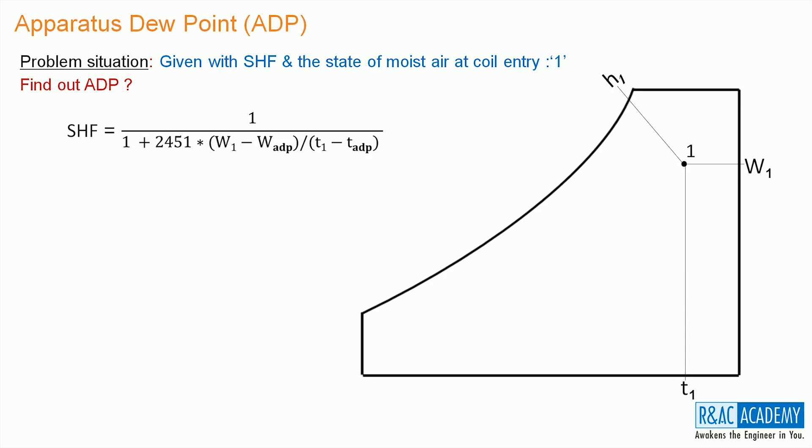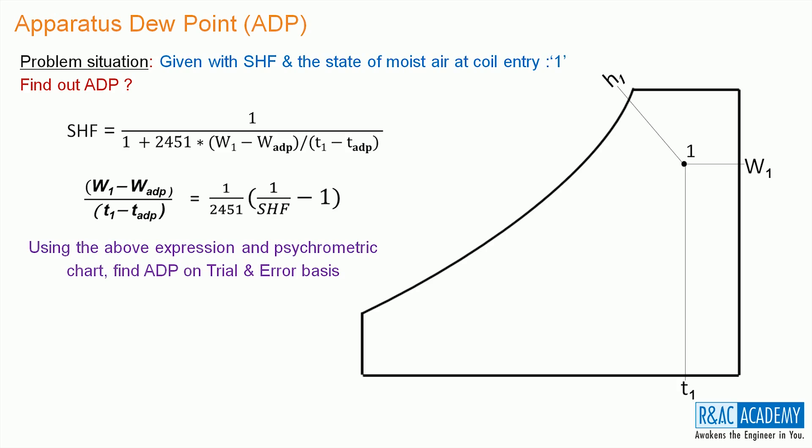We have the expression for SHF which can be rearranged. We know T1, W1 and SHF in this expression. Using the above expression and the psychrometric chart, we can find the ADP on trial and error basis or using iterative method. Assume a temperature T and collect the corresponding W value from the chart. Then, substitute the T and W values in this expression against TADP and WADP values respectively. Check whether the LHS and RHS values are equal.